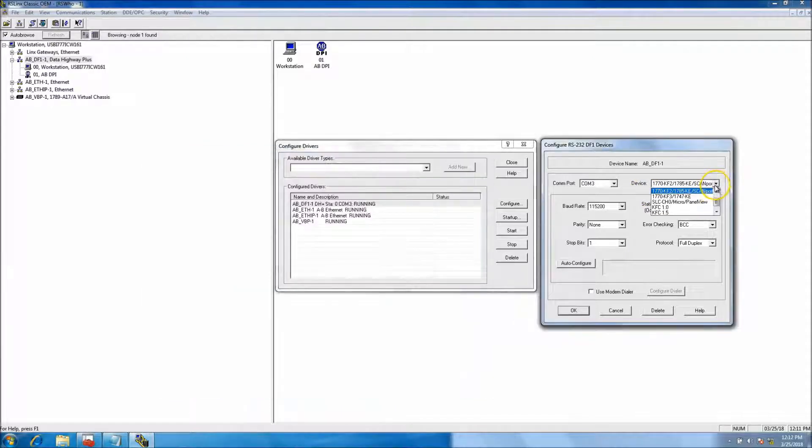I set the DF1 driver to scan port, then changed the baud rate to the maximum baud rate. My station number I put at zero — that's just what I put my computer driver at. Parity is none, error checking is BCC, stop bits is one, and the full protocol is full duplex. You can put it in half duplex — it's already a serial port so it's going to be slow.